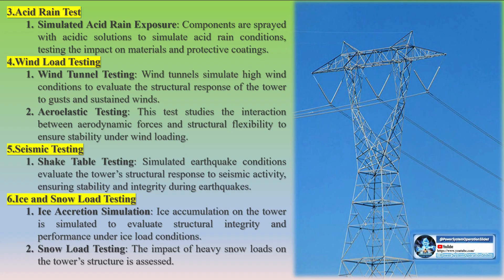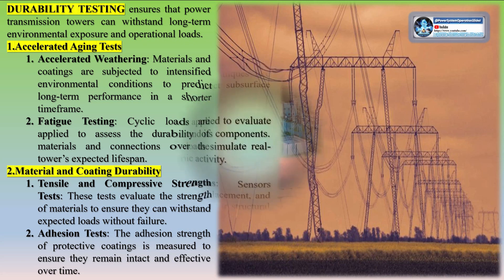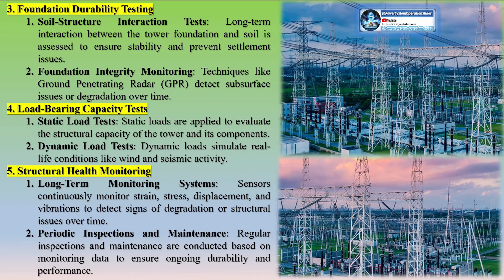Foundation integrity monitoring uses techniques like ground-penetrating radar (GPR) to detect subsurface issues or degradation over time. Load-bearing capacity tests include static load tests, where static loads are applied to evaluate the structural capacity of the tower and its components, and dynamic load tests, which simulate real-life conditions like wind and seismic activity. Structural health monitoring uses long-term monitoring systems where sensors continuously monitor strain, stress, displacement, and vibrations to detect signs of degradation or structural issues. Regular periodic inspections and maintenance are conducted based on monitoring data to ensure ongoing durability and performance.